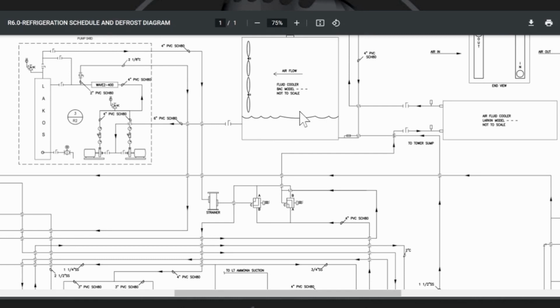Now, you also said at one point you guys do the blowdown, the reverse flow, every week. Yes. And how often is the Lakos then drained? Is that done when it backfeeds? It never drains. All it does is blow down once a day at 9 o'clock in the morning. We open that motorized valve for about 15 seconds and blow whatever is trapped in there at that point. And in the wintertime, it's really kind of a waste because there's nothing in it. Yeah. Because we're not evaporating any water, and the water's not exposed to the air, so there's no particles in it. But in the spring and summer and the fall, some crud gets blown out of it.